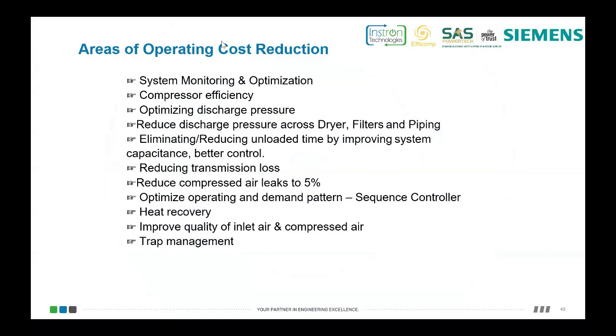In 90% of cases, you will find that out of the total saving, around 40% saving is done by either zero investment or very minor investments, which can be recovered within 6 months and can be allocated from the maintenance budget itself. The technology comes into picture when there is any replacement, and the highest cost of replacement in a system is the compressor itself.